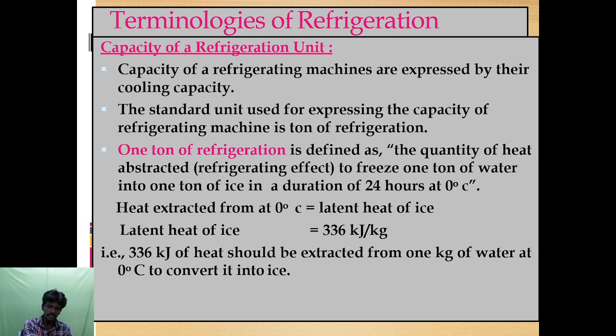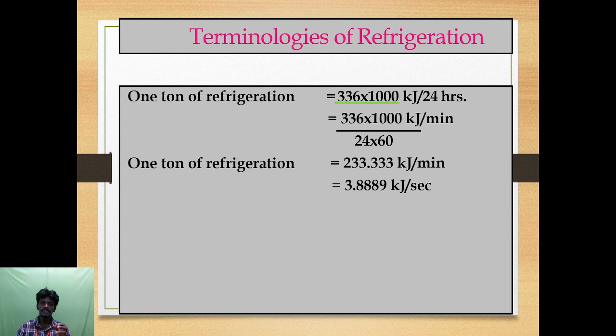The latent heat of ice is equal to 336 kilojoules per kilogram. For each kilogram we remove 336 kilojoules to convert the water into ice. That is called the latent heat of ice. This is the formula: 1 ton of refrigeration equals 336 into 1000 kilojoules per 24 hours. Hours are converted into minutes, so divided by 24 into 60, we get 233.33 kilojoules per minute, which equals 3.8889 kilojoules per second. This is the terminology of refrigeration.